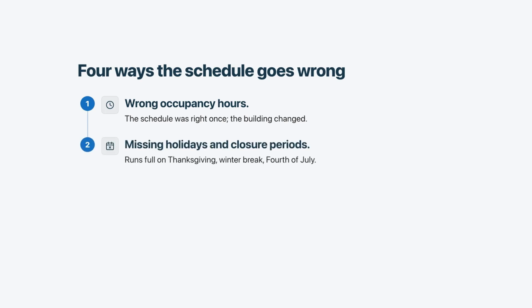A second one is missing holidays. A commercial HVAC system will happily condition an empty building over Thanksgiving, on Christmas, 4th of July, and during the entire winter break at school because the holiday schedule was never filled in or has been wrong for years. For a school, this alone can be 10 to 12 weeks a year of fully scheduled HVAC with no occupants.